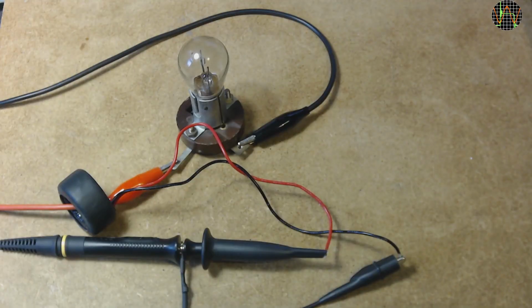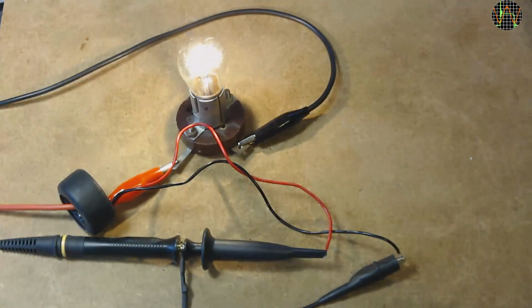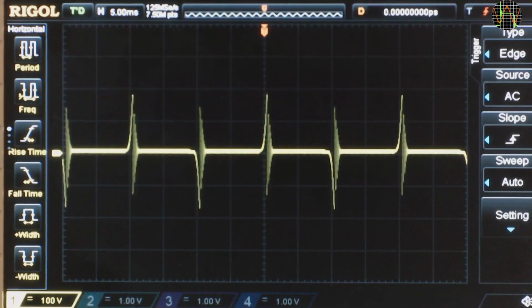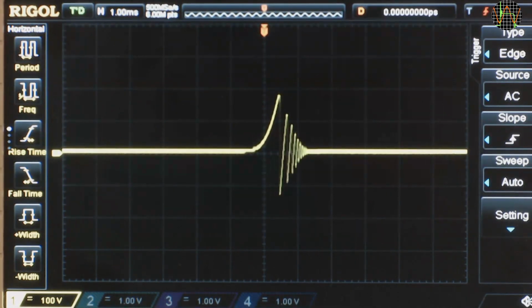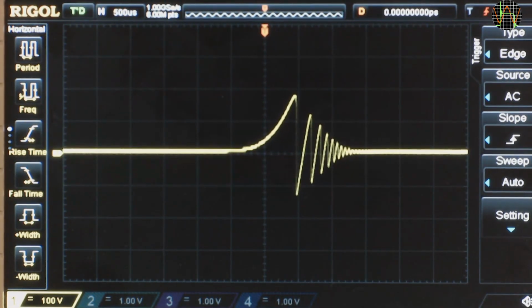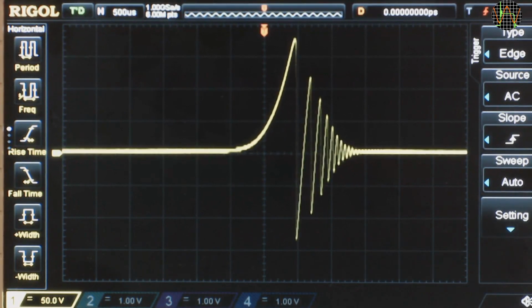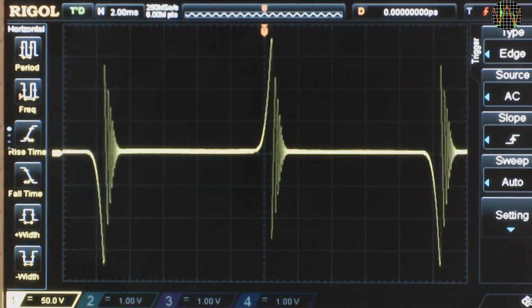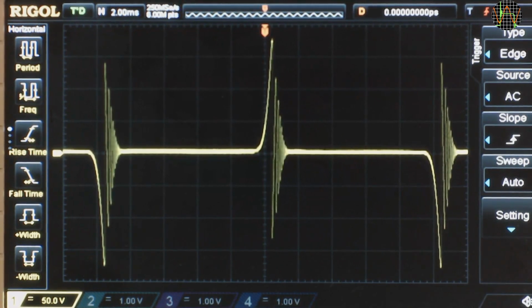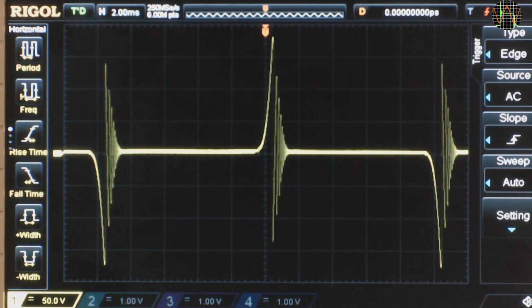So I disconnected all the meters and connected a scope probe directly to the open coil. No wonder the meters disagreed on the displayed RMS value. The voltage consists of just spikes. And look at the amplitude. Each horizontal line on the scope is 100 volts, so we have 300 volts peak to peak. I guess Wikipedia was right in warning of high voltage on an open current transformer. You can see how the spikes correspond with the positive and negative half waves, and each high voltage spike is then followed by this oscillation of the voltage settling down to zero.